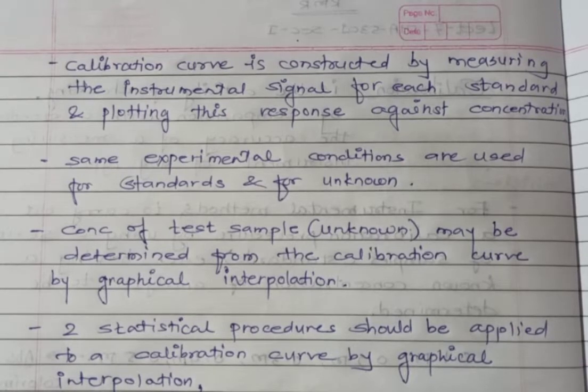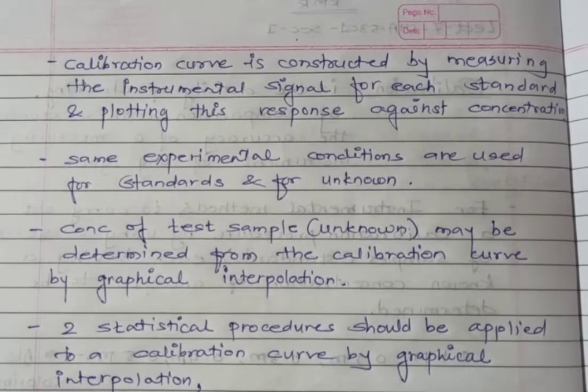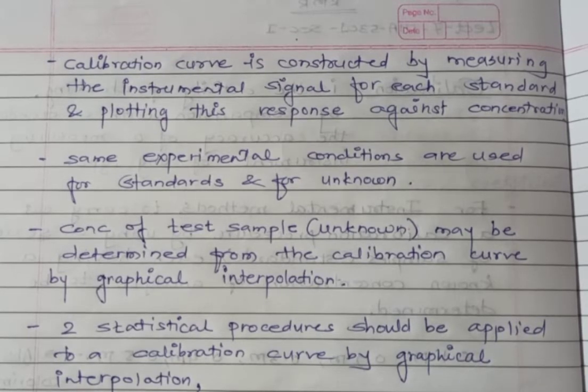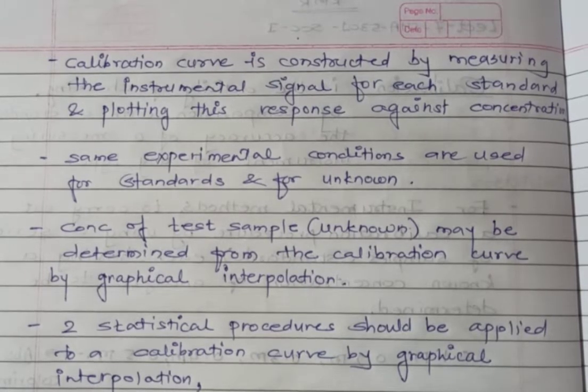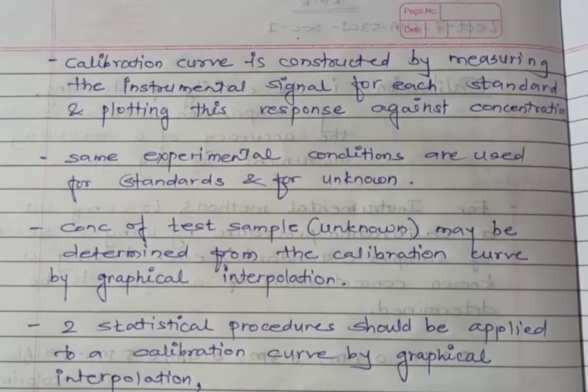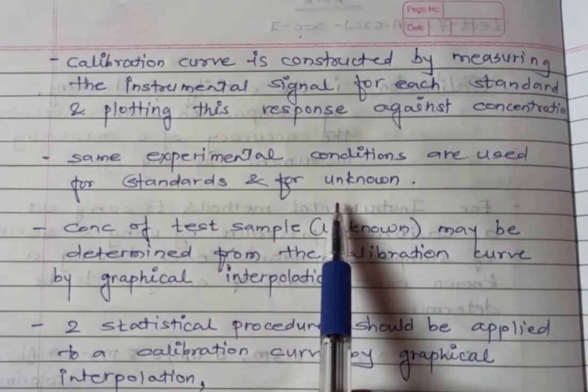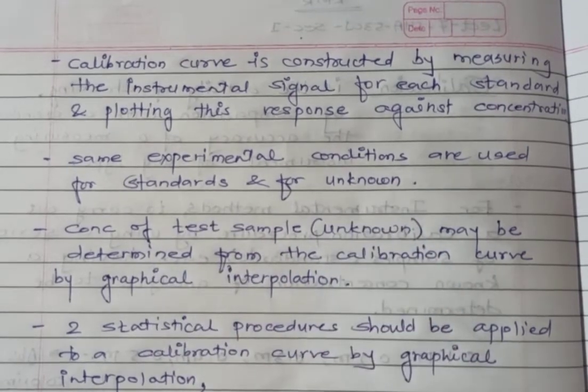That means y is directly proportional to x. You then put one unknown solution into the instrument and measure its signal. The absorbance or percent emission intensity observed on the flame photometer is read on the y-axis, and by interpolation of the line you can identify the concentration of the unknown substance. The same experimental conditions are used for standards and for the unknown — same environment, same instrument, same solutions — so every parameter is equal for both.